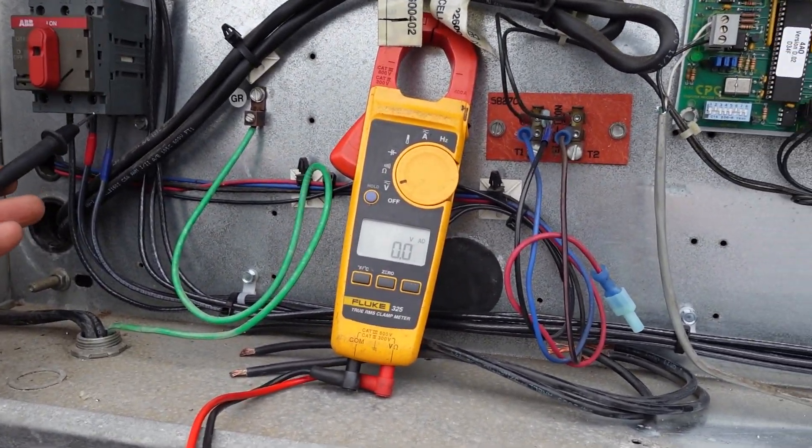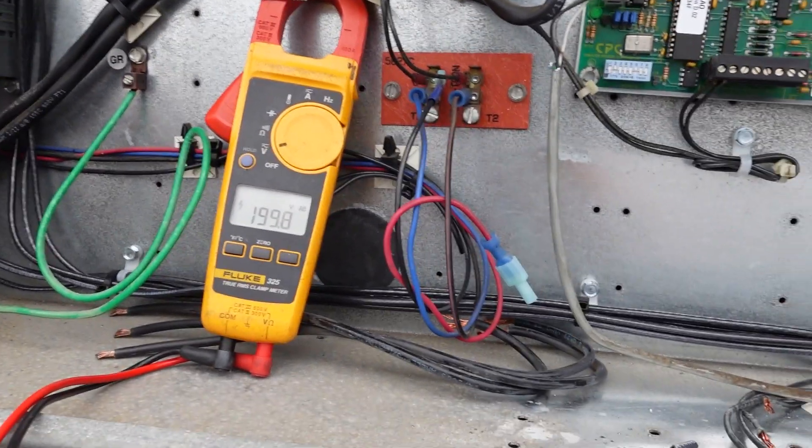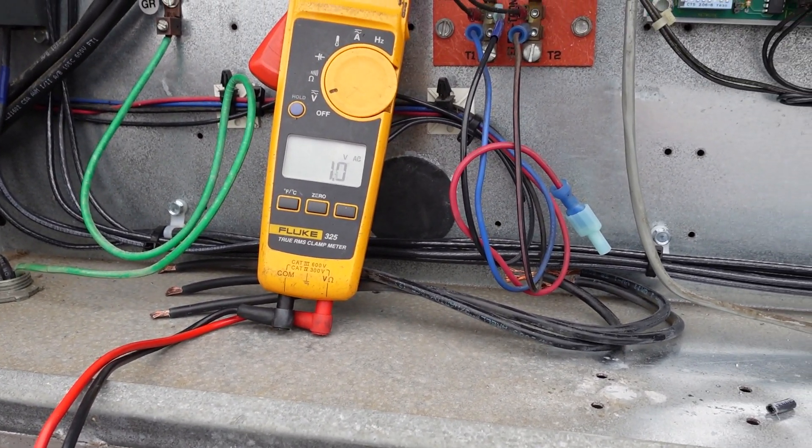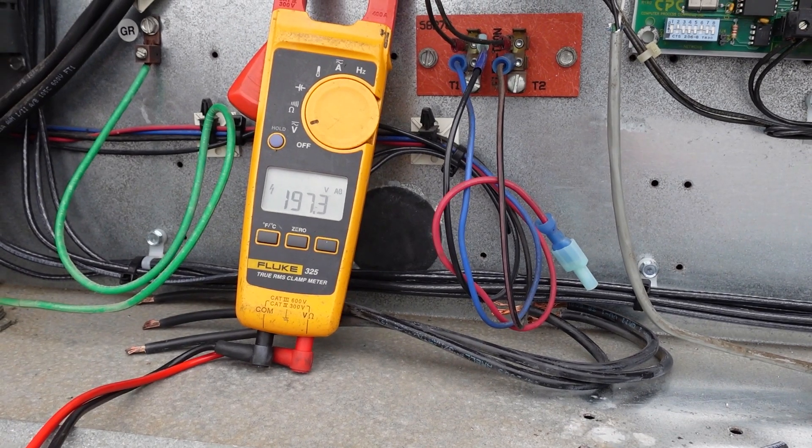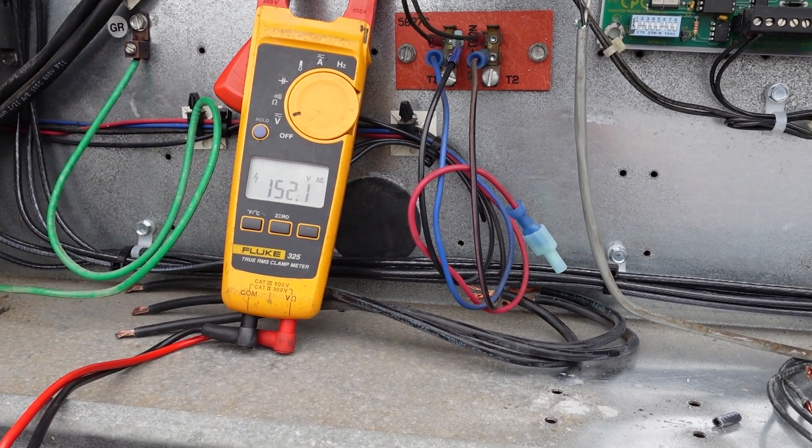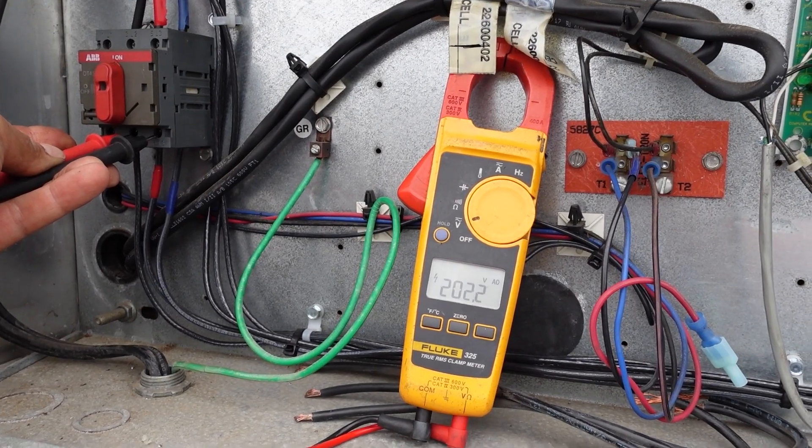Let me show you what I mean by that. So here's our meter, here's our incoming power, line one to line three, 201. Line one to line two, 197. Two to three, 202. That's on our disconnect coming in.